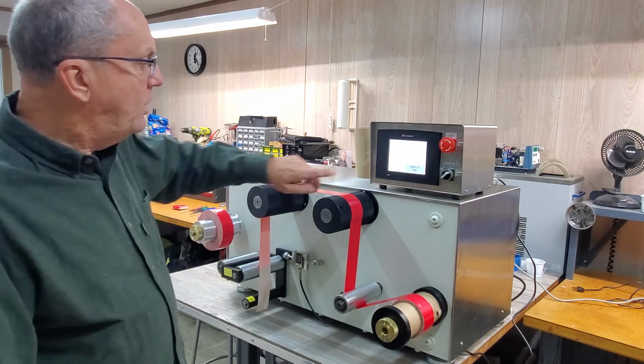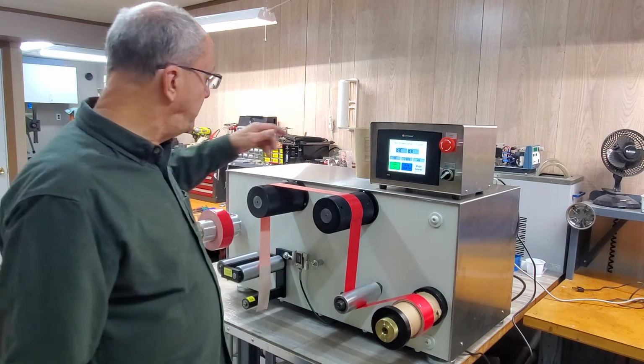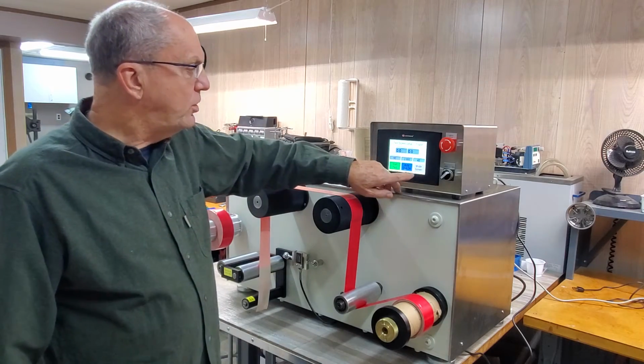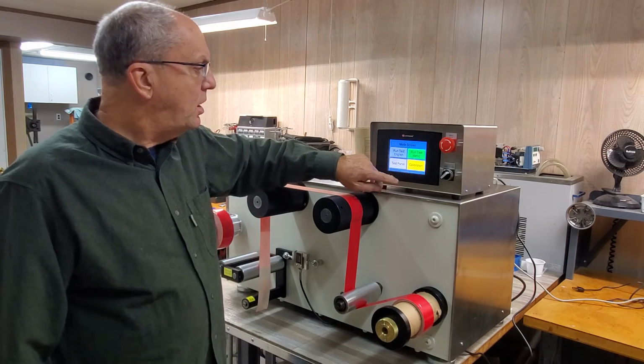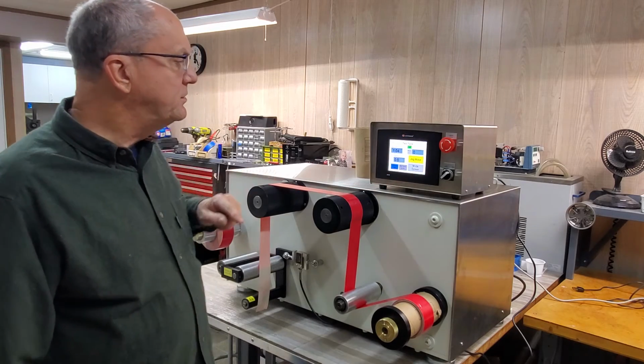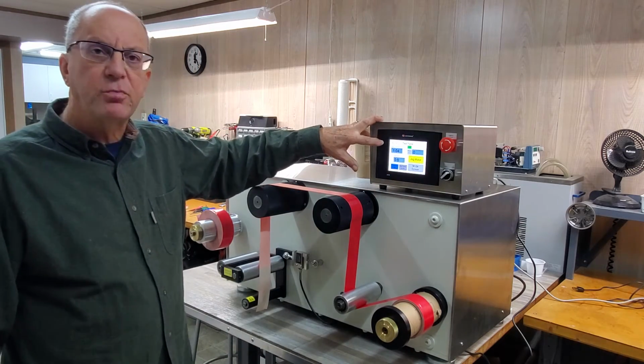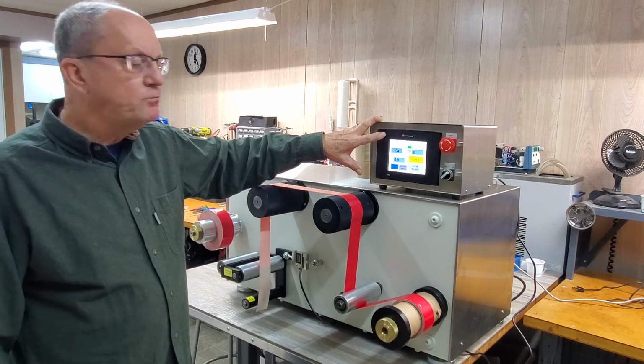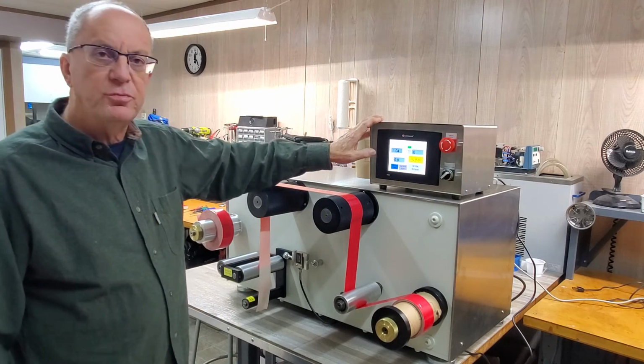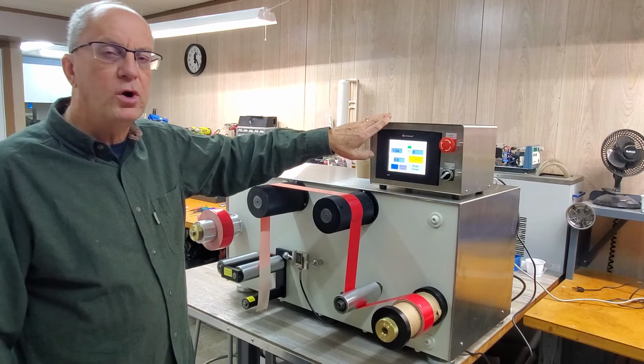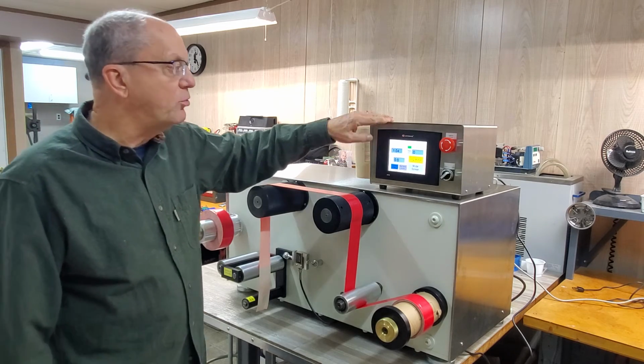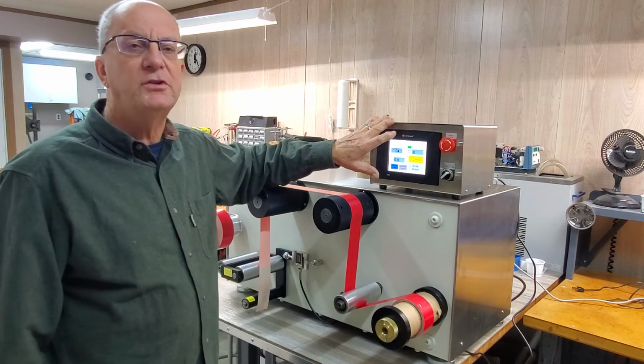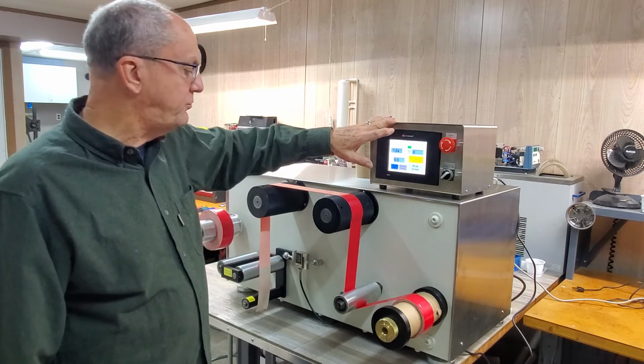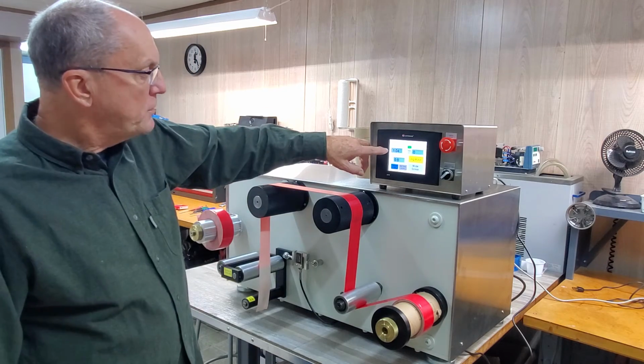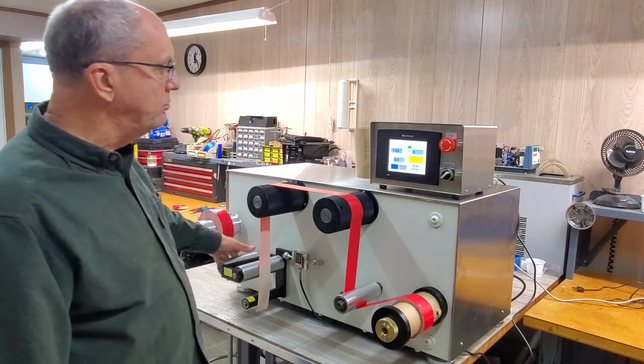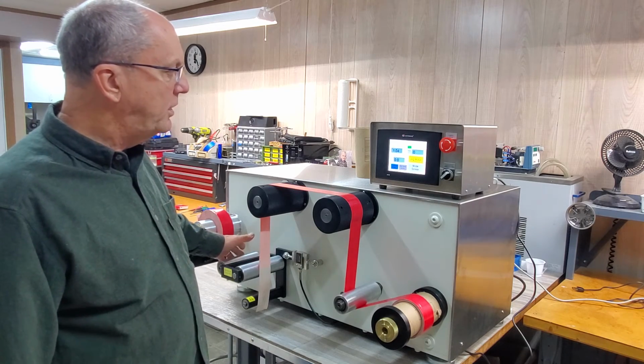So enough about that. Now, one other thing I just want to show you is we have a troubleshoot area in here, which we call the test panel. In the test panel, we essentially have a live display of all of the I/O that's involved with this machine. And this is good for troubleshooting and for setup and calibration and so forth. There's really no need to go into this test panel unless you suspect that you have some type of problem. But for example, I have the actual voltage coming out of the load cell, and if I squeeze that, it goes up. If I let it go, it goes down.